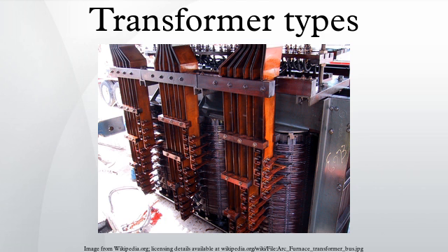Terminal identifications indicate one end of each winding, indicating the same instantaneous polarity and phase between windings. This applies to both types of instrument transformers. Correct identification of terminals and wiring is essential for proper operation of metering and protective relay instrumentation. Current transformer. A current transformer is a series-connected measurement device designed to provide a current in its secondary coil proportional to the current flowing in its primary.